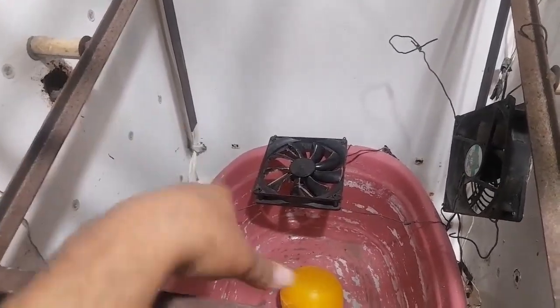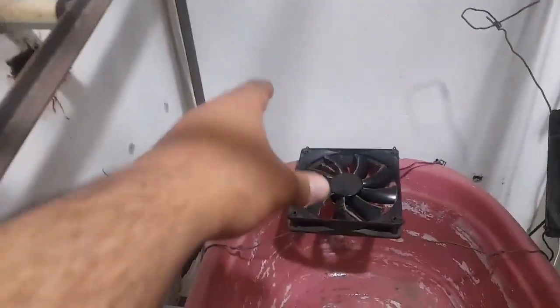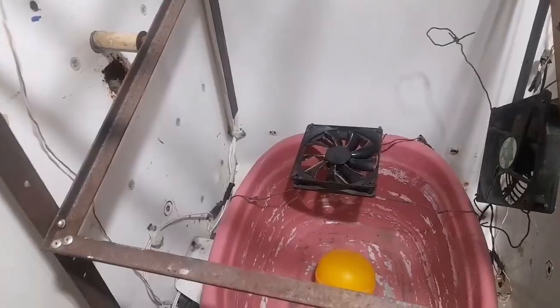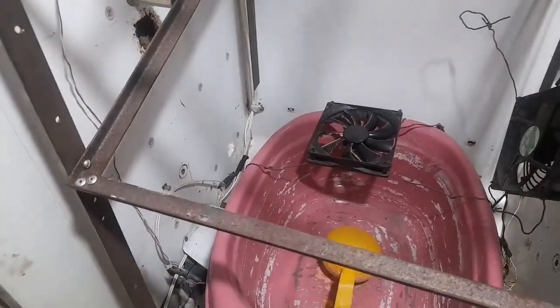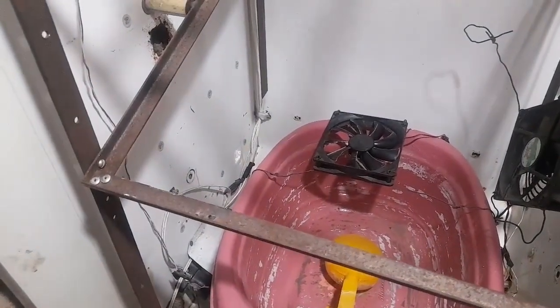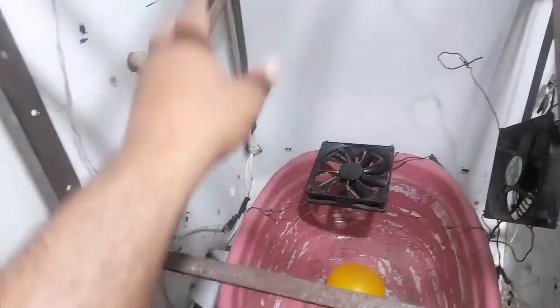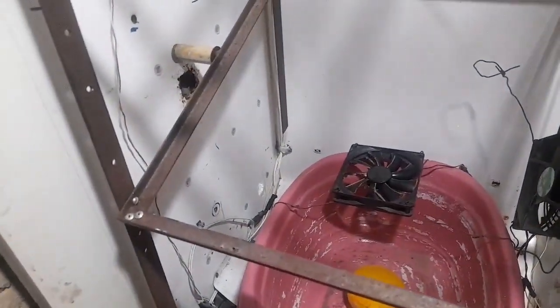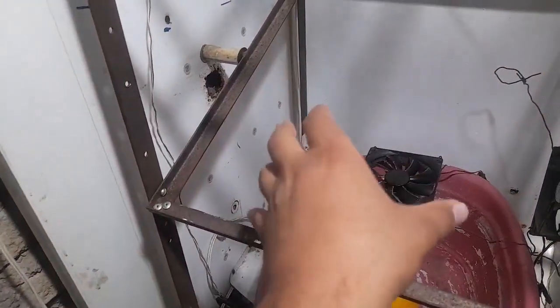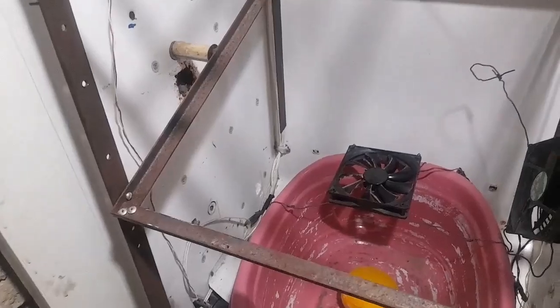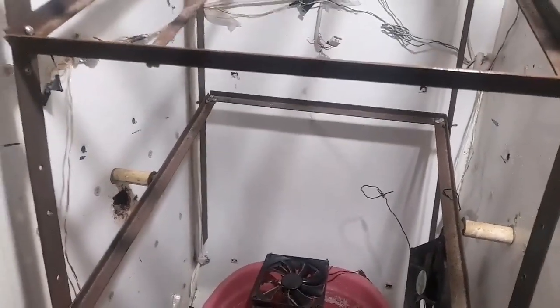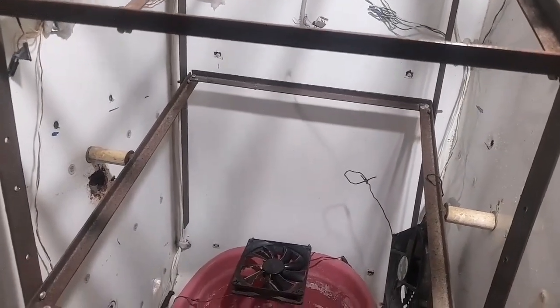Second, they continuously circulate the air inside the incubator. Good air circulation keeps both the temperature and humidity uniform in every part of the cabinet. Third, they help keep the air cleaner. Dust and small airborne particles tend to settle into the water instead of remaining suspended inside the incubator. So these fans don't just control humidity, they also improve overall air quality.